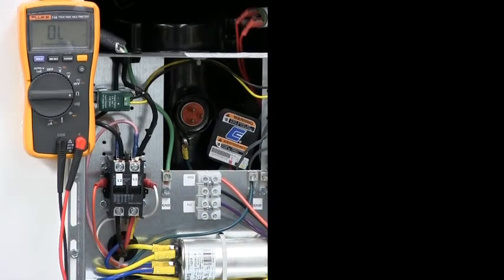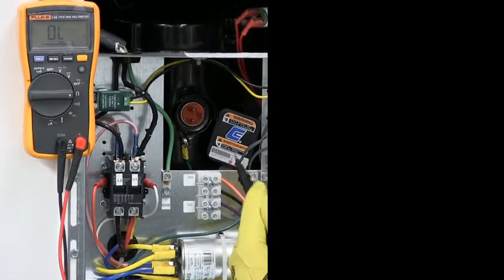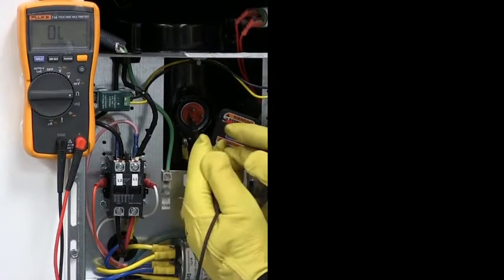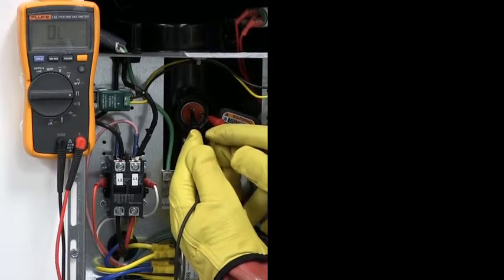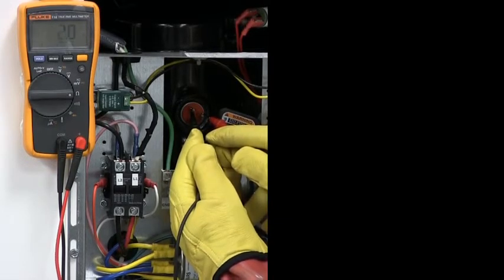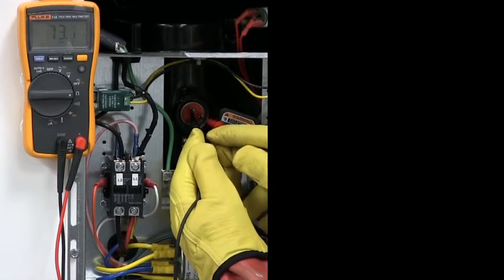You'll want to put your meter on the lowest ohm setting and check the resistance between the common and the start winding. It should be between 1 and 3 ohms. As we can see on the meter, we're looking at about 2 ohms, so that one's good.